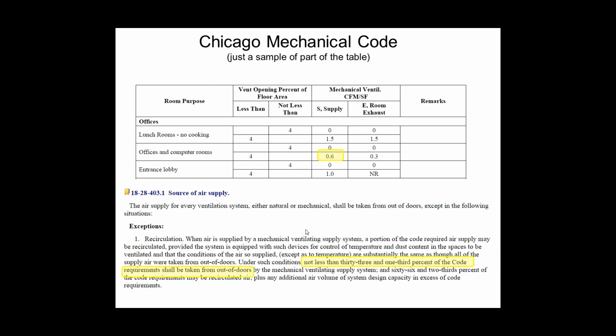Wisconsin is the opposite. Wisconsin says we don't care about the square footage at all. We want 7.5 CFM per person as a flat rate for all of our spaces. So in Wisconsin, there's hardly any outside air requirement. Chicago has the most of anywhere, and everybody else is in the middle. But just keep that in mind.